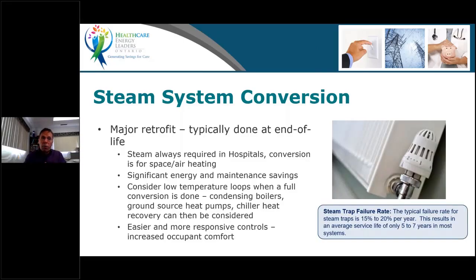Talking about steam traps, if you said, "Oh, it's okay, my steam traps were checked 5 years ago," that is not okay. They fail about 15 to 20% per year with a typical lifespan of 5 to 7 years. So that's something you have to do on a continuous basis. That's periodic, and it's not every 5 years.